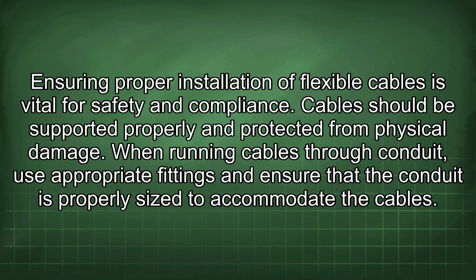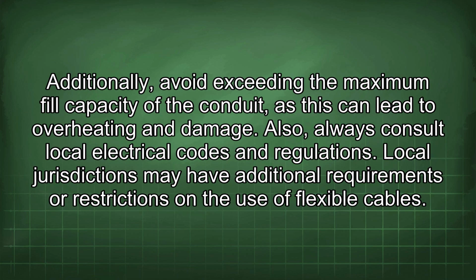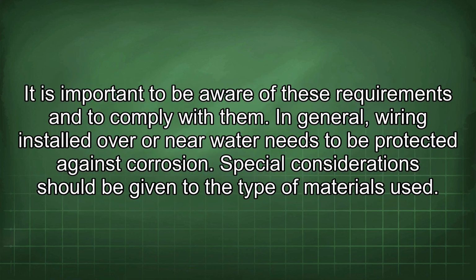Cables should be supported properly and protected from physical damage. When running cables through conduit, use appropriate fittings and ensure that the conduit is properly sized to accommodate the cables. Additionally, avoid exceeding the maximum fill capacity of the conduit, as this can lead to overheating and damage. Also, always consult local electrical codes and regulations. Local jurisdictions may have additional requirements or restrictions on the use of flexible cables. It is important to be aware of these requirements and to comply with them.